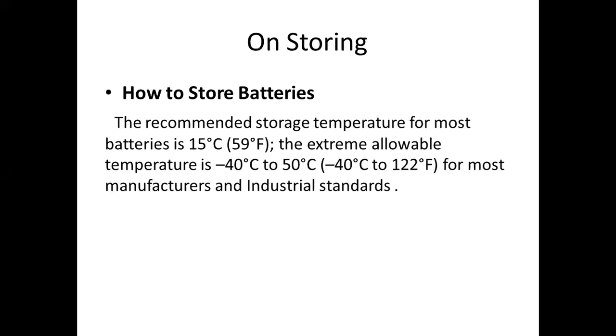Sometimes it goes beyond, because when it comes to huge battery systems, like 100 or 200 batteries, 50 to 200 single cells are connected, and I'm making a battery pack. That can't be given at 50 degrees Celsius, so that should be reduced again. So based on the size and electrical parameters of the battery, the temperature allowable range changes. This is for one of the most common manufacturers and industrial standards.